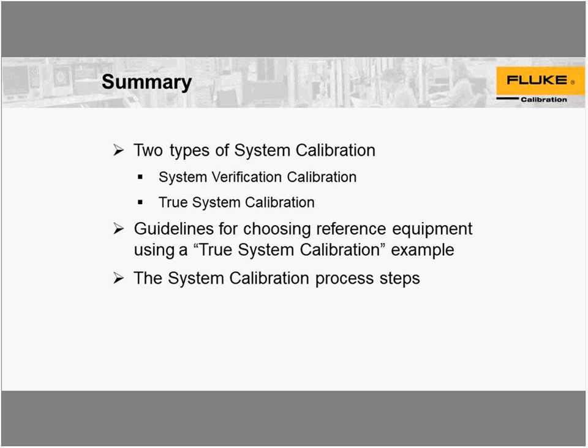Next question is, would it be wise to have a higher accuracy standard in-house to perform a calibration verification of our Fluke 1552A before using it as a standard for calibrating equipment? Yeah, it actually would be wiser to have a higher accuracy standard with better uncertainties to calibrate a Fluke 1552. I also do a lot of those calibrations here in our lab, and we use a 1595A and a 5699 to calibrate the stick thermometers as well. You probably could do that with a Black Stack, and a 5628 would probably be very close. Not quite as good as a super thermometer and an SPRT, but it should be sufficient to do that.